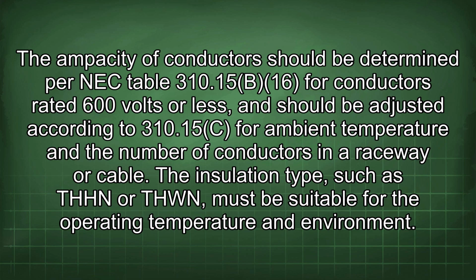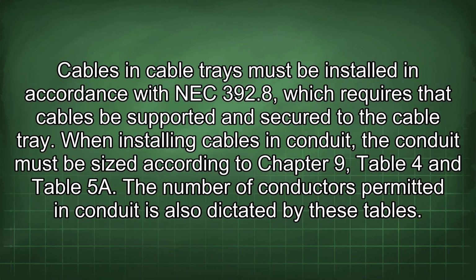The insulation type, such as THHN or THWN, must be suitable for the operating temperature and environment. Cables in cable trays must be installed in accordance with NEC 392.8, which requires that cables be supported and secured to the cable tray. When installing cables in conduit, the conduit must be sized according to Chapter 9, Table 4 and Table 5A. The number of conductors permitted in conduit is also dictated by these tables.